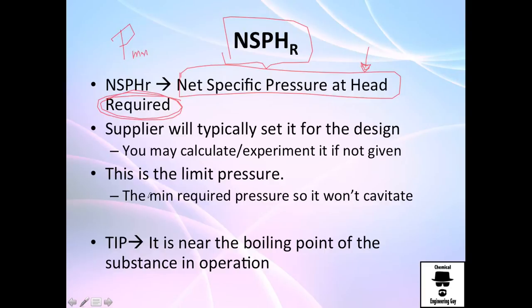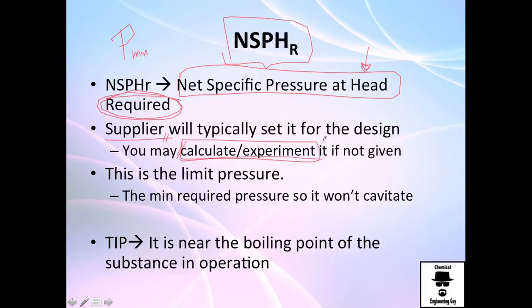This minimum pressure to avoid cavitation can be calculated experimentally, but you don't want to do that because it means forcing your pump into cavitation. So this data is already provided by the supplier — it's in the manual along with typical performance data: power requirements, maximum RPM, maximum impeller diameter, and so on. You will find the NPSH requirements there. If you don't have supplier data, you'll need to determine it yourself, but it is essentially a minimum limit pressure before the fluid enters the pump.